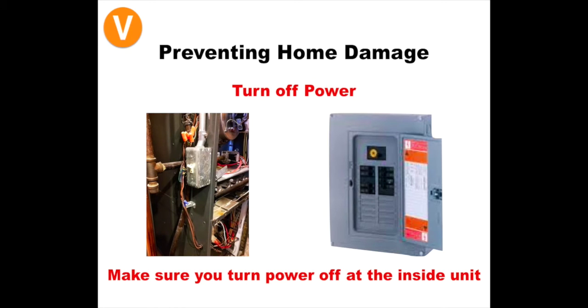All right, so the next step to preventing a home damage is turning off power. Now, this is one of the most obvious steps to an install, but it's one that gets forgotten, or it's done incorrectly a lot of the times, and we get a lot of home damages from that. The most common home damages that come from this are blown fuses and blown transformers. Now, if we turn the correct power off to a system, your chances of blowing a fuse or a transformer drop dramatically, because once you turn power off, you've killed power to the wires, and now it doesn't matter if wires are touching, you're not going to short anything out. But if you turn the wrong power off, or you don't turn power off at all, it takes just for the R and the C wire to get close to each other, and that can cause a direct short on the transformer, and that's where we see fuses and transformers getting damaged. So make sure we're turning off the power.